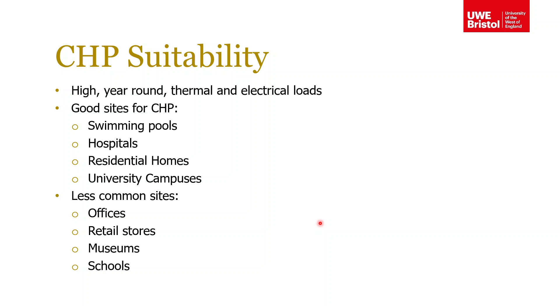The places where CHP is really good are sites that have a high thermal load and a high electrical load year-round. Good sites include swimming pools — think of all the hot water used in a leisure centre — along with hospitals, which similarly have high thermal and electrical loads.